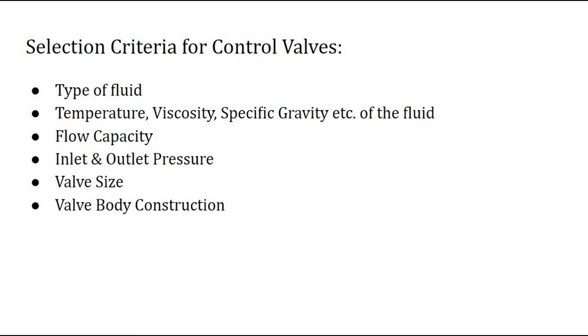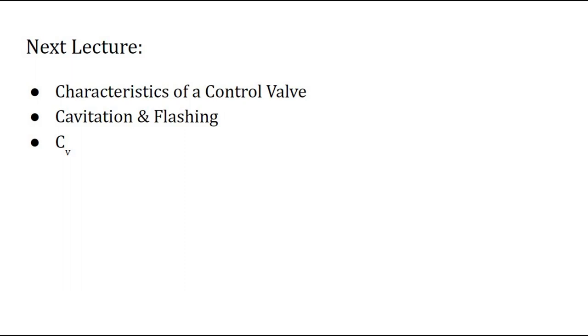Now that we have covered the different types of control valves with their advantages and disadvantages, let us look at the selection criteria for control valves. Before selecting a control valve, we consider: the type of fluid passing through the valve, the temperature, viscosity, specific gravity, and other fluid parameters. We also consider the flow capacity of the valve, the inlet and outlet pressure, the valve size, and the valve body construction. In the next lecture, we will cover the characteristics of control valves, cavitation and flashing, and the valve coefficient CV.